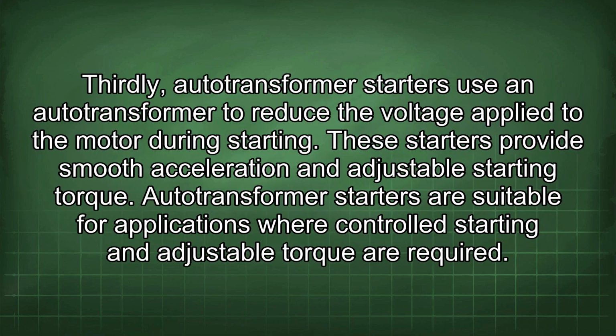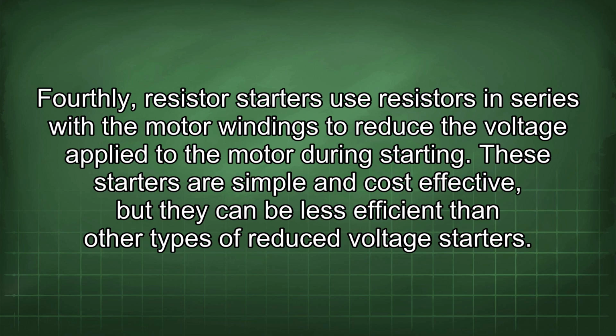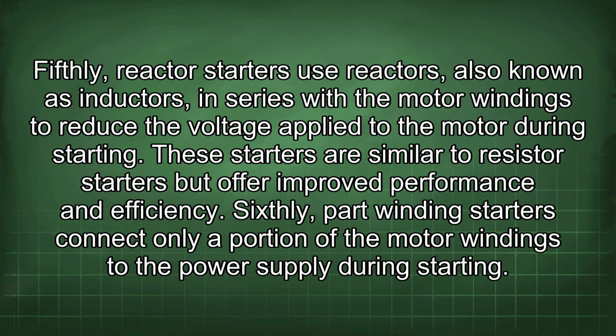Thirdly, autotransformer starters use an autotransformer to reduce the voltage applied to the motor during starting. These starters provide smooth acceleration and adjustable starting torque. Autotransformer starters are suitable for applications where controlled starting and adjustable torque are required. Fourthly, resistor starters use resistors in series with the motor windings to reduce the voltage applied to the motor during starting. These starters are simple and cost-effective, but they can be less efficient than other types of reduced voltage starters. Fifthly, reactor starters use reactors, also known as inductors, in series with the motor windings to reduce the voltage applied to the motor during starting. These starters are similar to resistor starters but offer improved performance and efficiency.